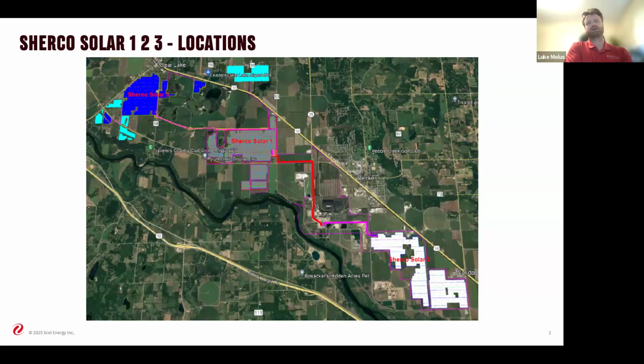From experience operating Sherco 1 since October, you do see clouds roll over, and it's surprising how fast the outputs change. If you watch a very large cloud or multiple large clouds roll over, you can watch in real time inverters go from 3,600 kilowatts down to 1,800, back up to 3,400, down to 1,800 again, then down to 1,400 and back up to 2,800. So the clouds cause quite a bit of variation, but the overall output is pretty well levelized on average. Keeping the blocks together makes it a little easier to predict your outputs, since you don't know how wind direction will affect the clouds across a spread-out site.